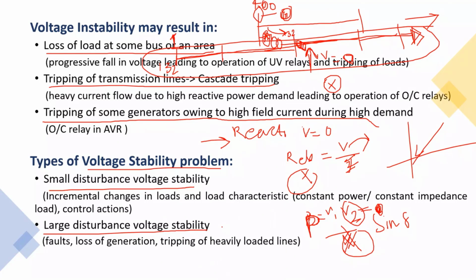One thing we should know is that whether it is voltage stability, angular stability or frequency stability, any one of them can encroach on the other areas and result in another kind of instability problem. Let us say a load-generation balance issue. If there is a significant load, frequency will go down. If the load is very high, many transmission lines will be overloaded, due to which their voltages will be low. And at the same time, if the voltages are on the lower side and you have to transfer the same amount of power, then with P = V1 V2 / X * sin delta, that sin delta will be high, right?